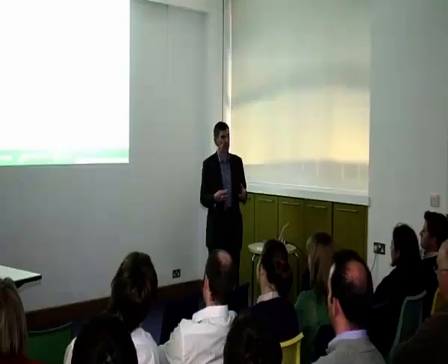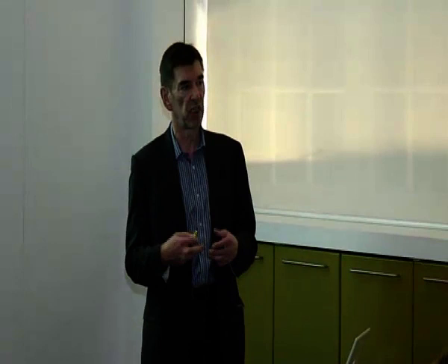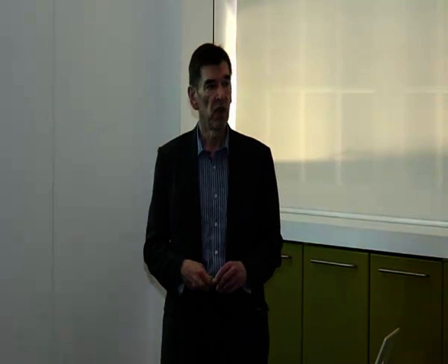In the questions that we were asked for the Glasgow Transport Museum, you can see here these are fairly wide-ranging. A lot of them related specifically to a gallery where you get close control conditions. We had to convince the client that this novel design - this huge volume - could actually work as an air-conditioned space and do it sustainably with some control over the energy consumption in that building. The question we're asking here is: how do we combat downdraft at the glazing? On the south elevation of the Glasgow Transport Museum the glazing is over 30 metres high, and on the north elevation it's over 20 metres high.